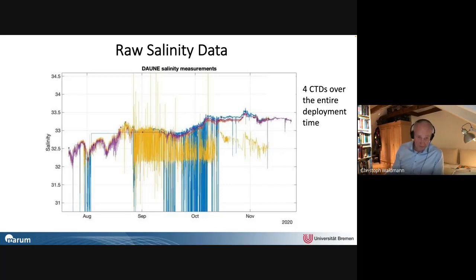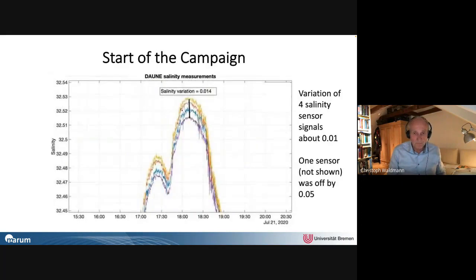But there are other manufacturers who are using open cells, with different configurations, and they are not good at all for that type of measurement. On the other hand, this is just something that I heard: in profiling applications, these open cells seem to perform better than the pump cells of Seabird. But Anna, don't nail me down on that, okay? It might be just individual experience.